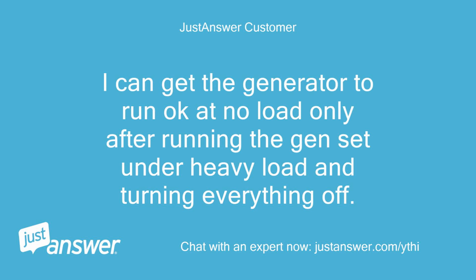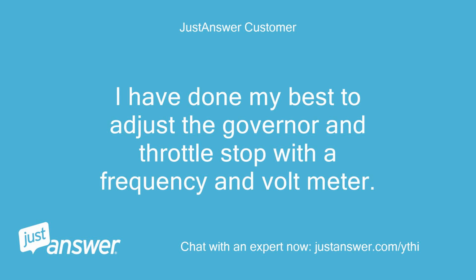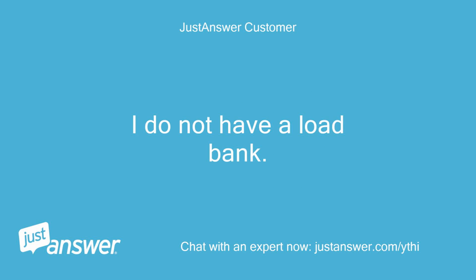I can get the generator to run okay at no load only after running the genset under heavy load and turning everything off. I have done my best to adjust the governor and throttle stop with a frequency and voltmeter. I do not have a load bank.